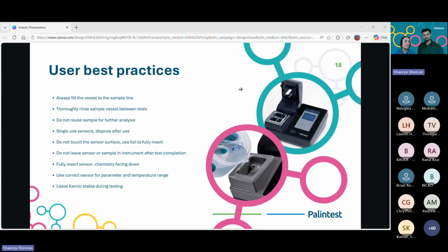Now, do not touch the sensor surface, so use the foil to fully insert. You will have noticed in the demonstration that I tore off the top half of the foil, inserting it into the instrument while holding the bottom half. If you do touch this, again, the chemistry is dosed on there and it will not give the correct result. Do not leave the sensor or sample in the instrument after test completion.